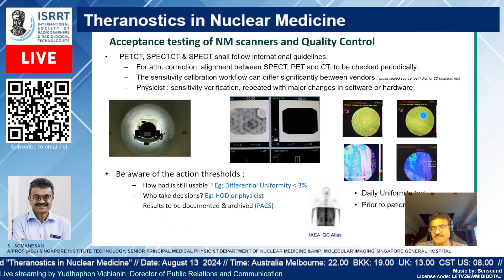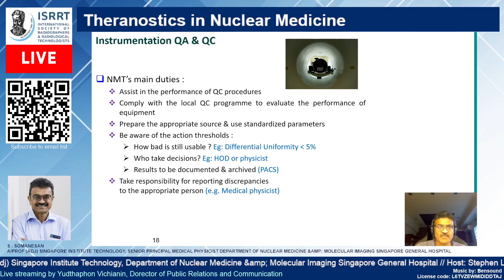Okay. And talking about implementation of QA/QC, in essence, if you look at the nuclear medicine technologists' main duties, it is to assist in the performance of QC procedures, comply with the local QC program that is developed by the institute or nationally accepted, prepare the appropriate sources, and use standardized parameters for patient acquisition, and to be aware of the action thresholds, for example, as we just spoke about, how bad is usable, etc.